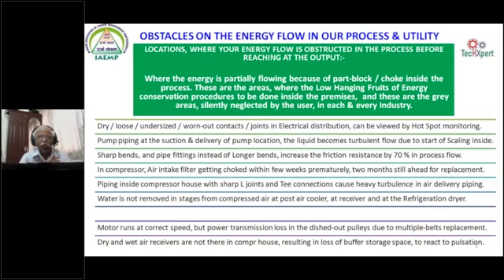That is why people go for VFD to trim down the losses because of the damper in the piping or the throttle valve in the piping. Then comes the sharp bends. See the sharp bends of the pipe fittings where you have very sharp bends, almost 70% more friction losses. This is thanks to the PCRA bulletins. They give a lot of inputs to us, energy inputs to the industry as such.